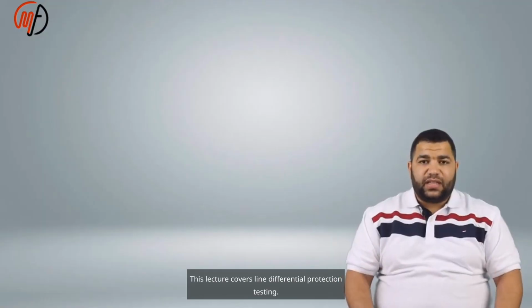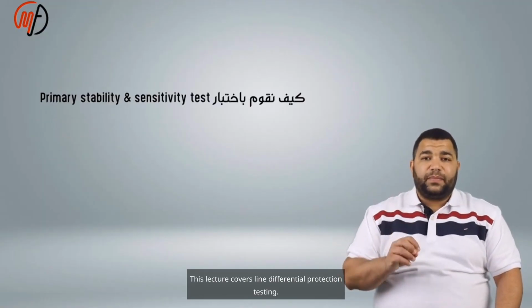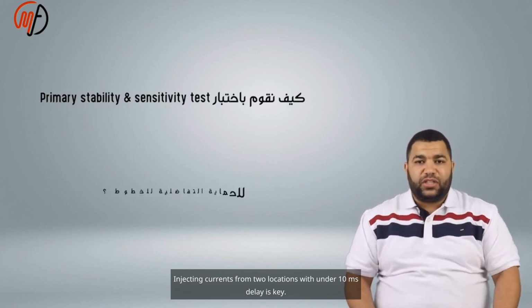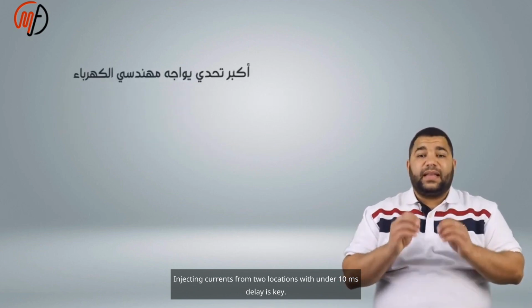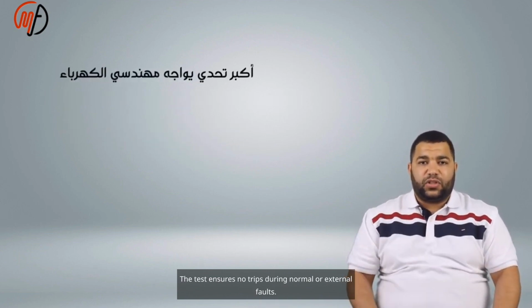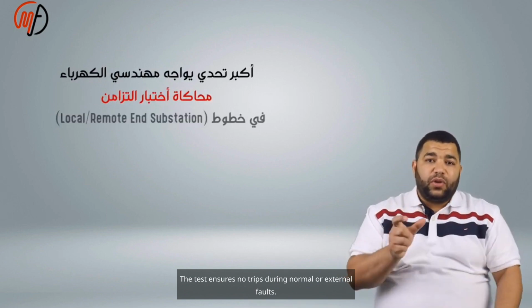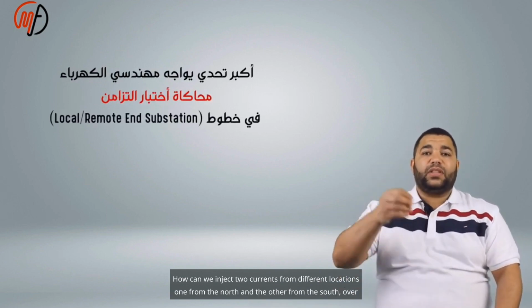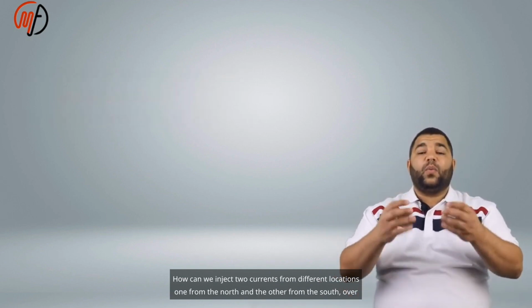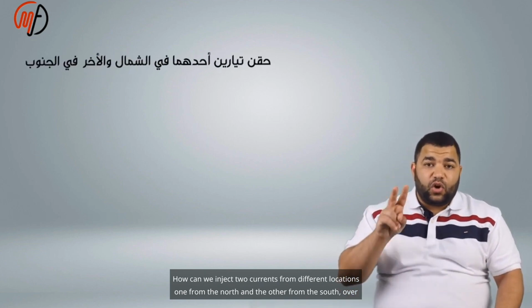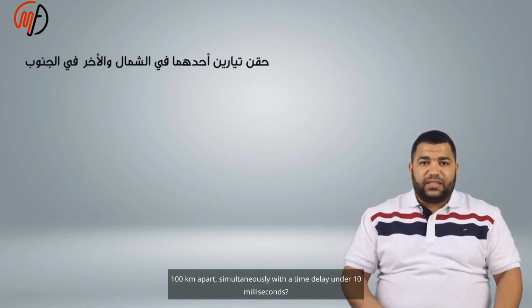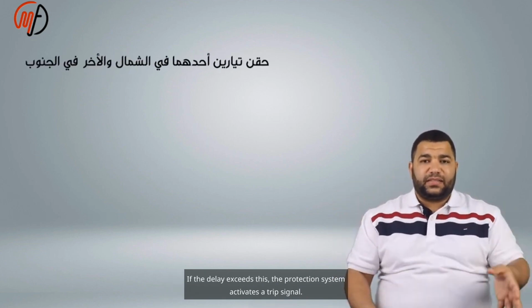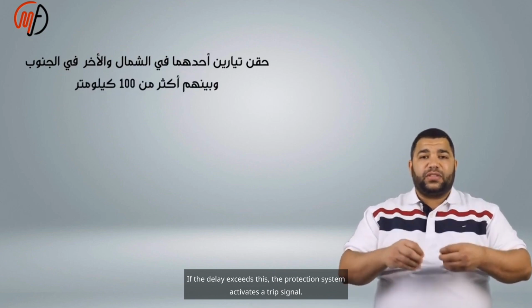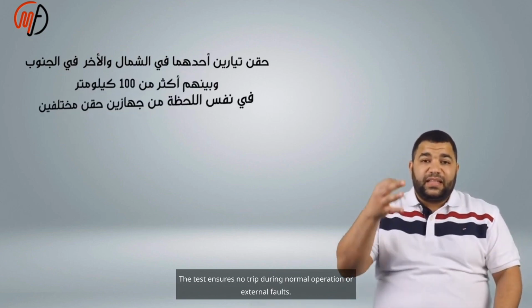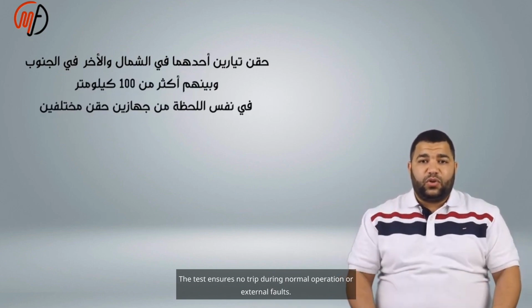This lecture covers line differential protection testing. Injecting currents from two locations with under 10 ms delay is key. The test ensures no trips during normal operation or external faults. How can we inject two currents from different locations, one from the north and the other from the south, over 100 kilometers apart, simultaneously with a time delay under 10 milliseconds? If the delay exceeds this, the protection system activates a trip signal. The test ensures no trip during normal operation or external faults.